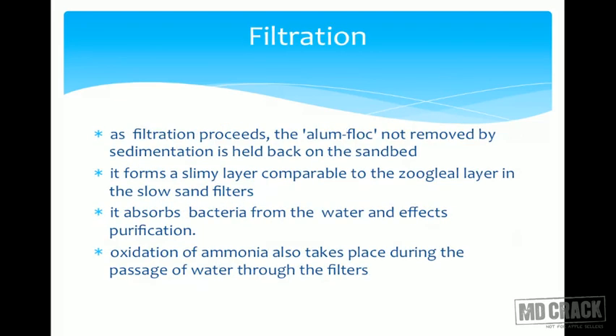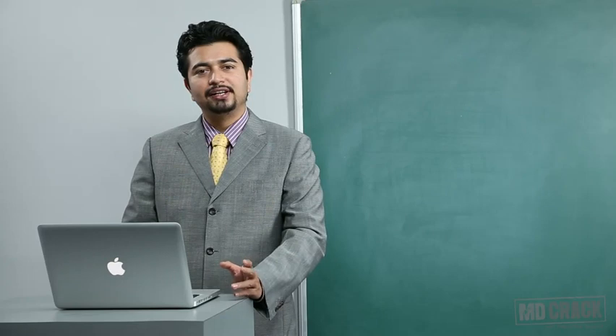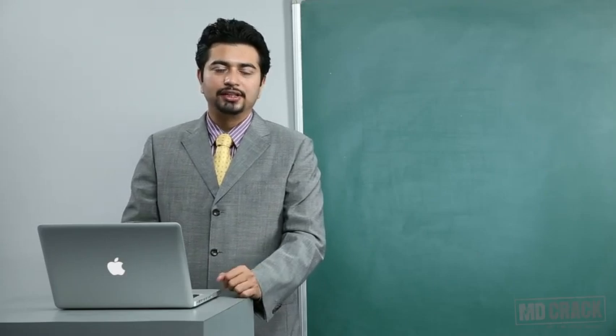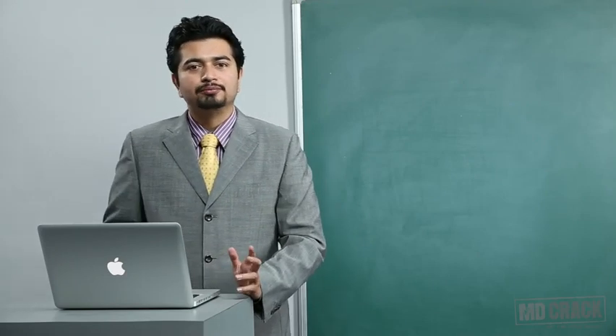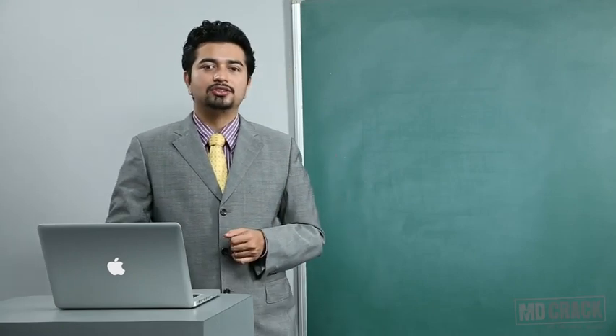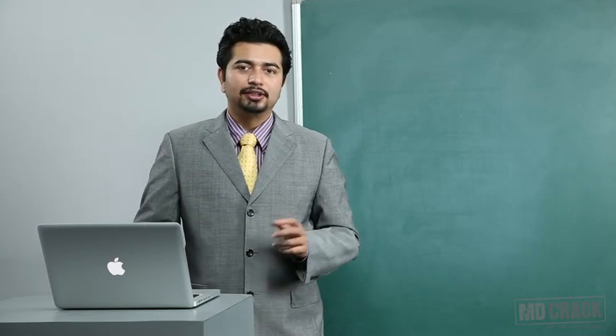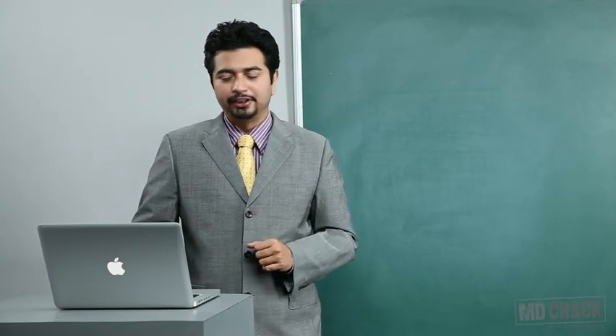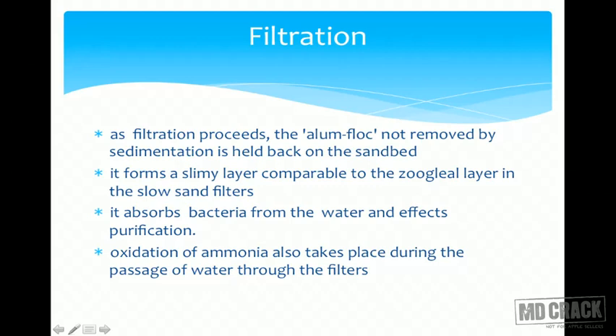Coming to the process of filtration: as filtration proceeds, the alum floc not removed by sedimentation is held back at the top of the filter. This alum floc layer above the sand filter is akin to the biological or zoogleal layer of the slow sand filter, although there is a great deal of difference between the two. The true biological layer in the slow sand filter did a lot of work, whereas this layer is not expected to perform those many functions.